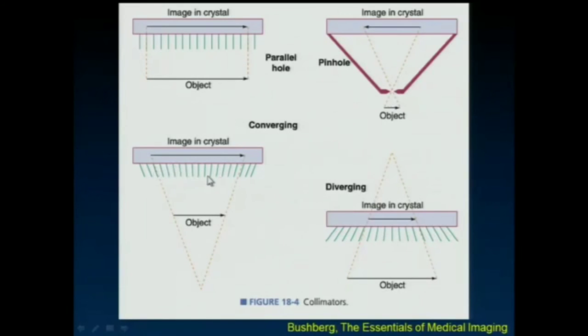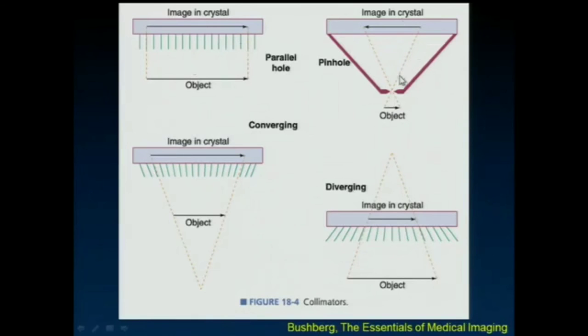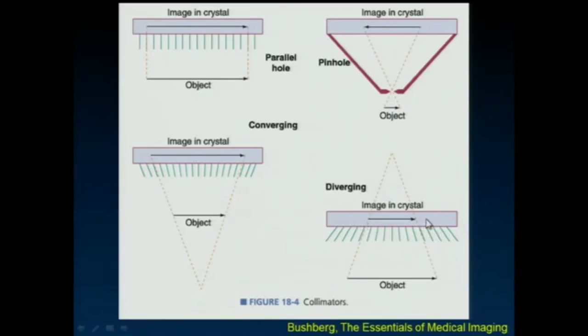A converging hole collimator has similar behavior to the pinhole, but the object doesn't get flipped and you can image closer to the object. A diverging hole collimator spreads out — the holes look at a larger field of view. Most nuclear medicine imaging is done with a parallel hole collimator. Pinhole collimators were used for thyroid imaging to magnify a small object. A diverging hole collimator was used on a portable camera for portable VQ scans in intensive care units, allowing a small camera to capture the large field of view of the chest.